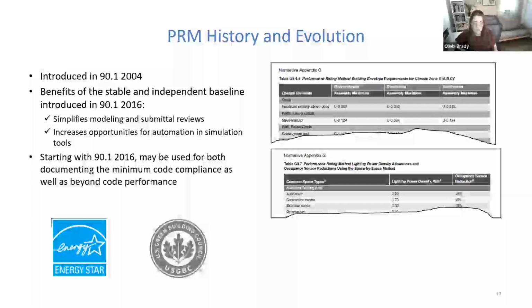In addition, the Appendix G baseline became more independent of the proposed design in this 2016 edition, in that the HVAC system types depend on just the building occupancy and climate zone. They no longer depend on the heating fuel source in the proposed design. And then starting with the 2016 edition, the performance rating method can be used for both documenting minimum code compliance and beyond code performance. Some examples of beyond code programs that use the 90.1 Appendix G include LEED for New Construction, the EPA Energy Star Multifamily New Construction Program, as well as many incentive programs in the Northeast.